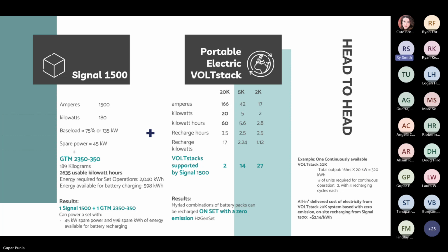If you look at the numbers we've got here, our standard delivery unit holds about 189 kilograms of hydrogen, which converts into about 2,600 usable kilowatt hours. The largest battery systems are on the order of 500 to 600 kilowatt hours, and they're really heavy and awkward to work with. Also, our basic unit is about the same size as a standard diesel genset, putting out around 180 kilowatts, whereas battery systems usually peak between 20 and 50 kilowatts. Those are very general numbers, on a case-by-case basis that'll change.